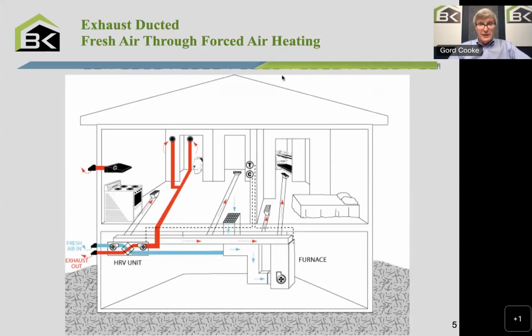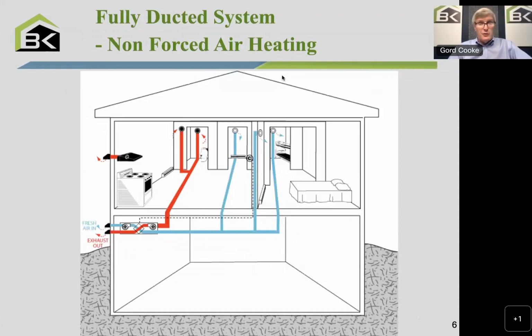You notice the red lines, the red ducts, are pulling air from wet areas, kitchens, bathrooms, those kinds of areas, and pulling that stale, moist air back and shooting it to the outside, recovering the energy from it. So that's a very common type of installation if you have forced air heating. Something to look for would be those 2 vents in the bathroom and kitchen, typically high in the wall, sometimes on the ceiling, that are exhausting air back to the HRV and sending it to the outside.